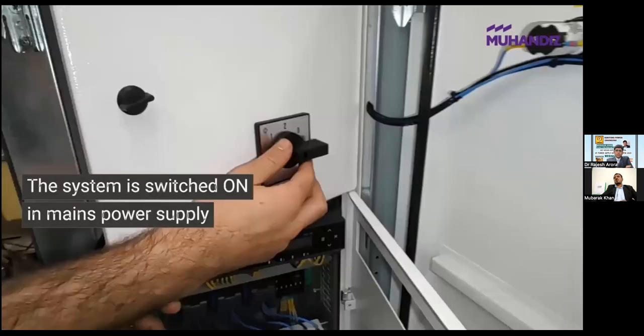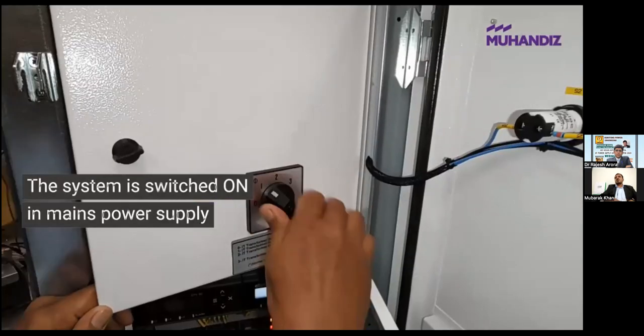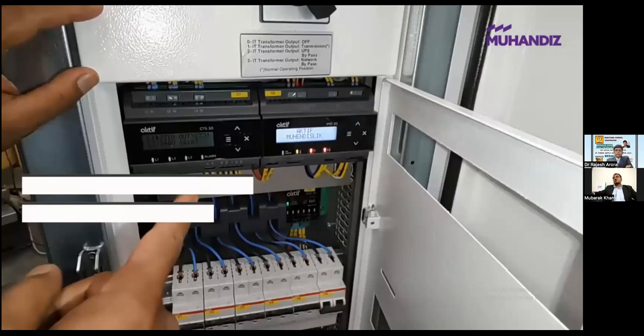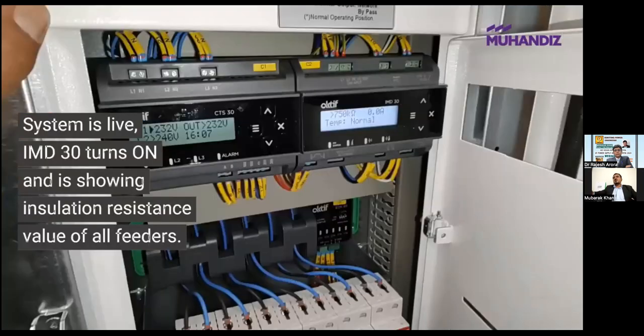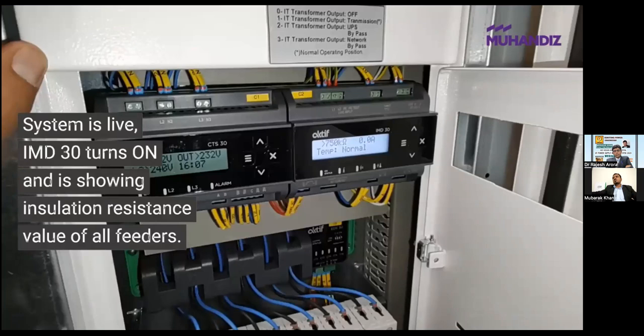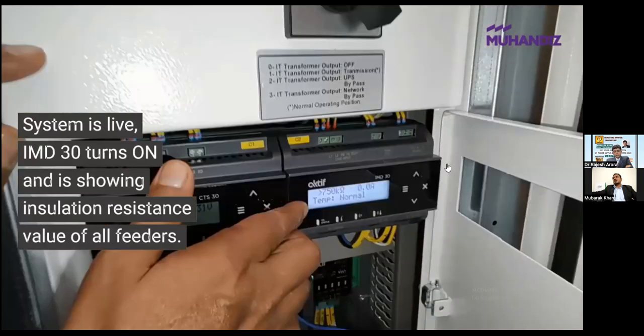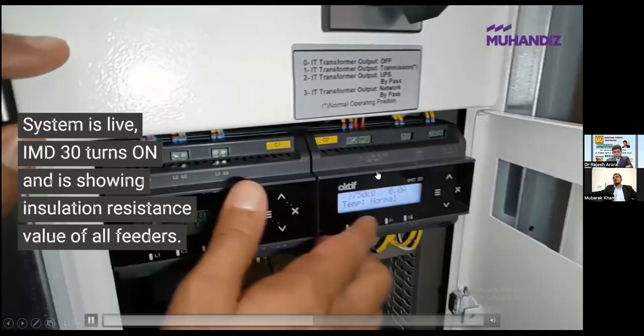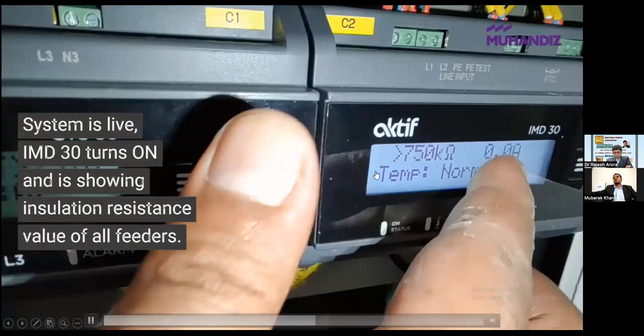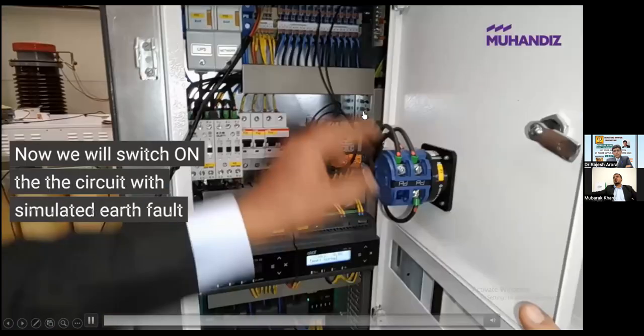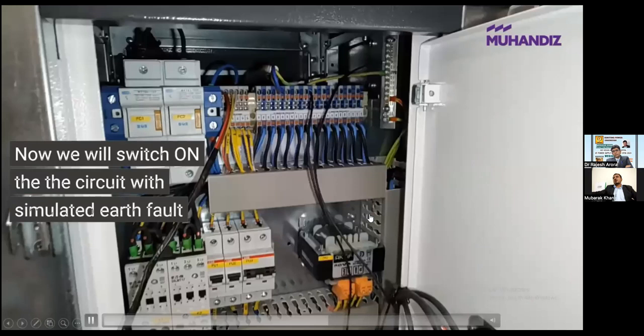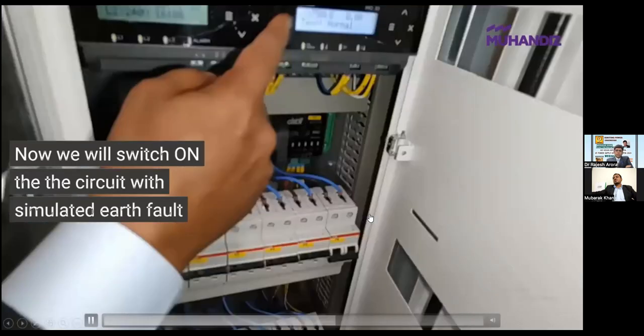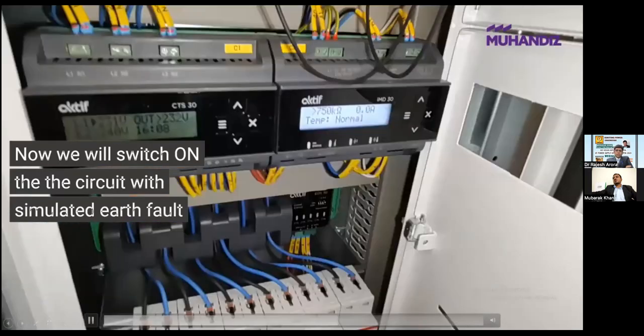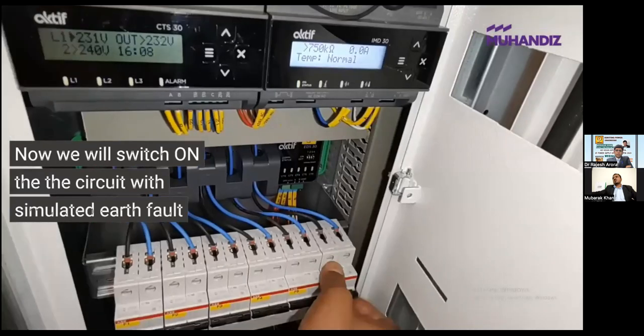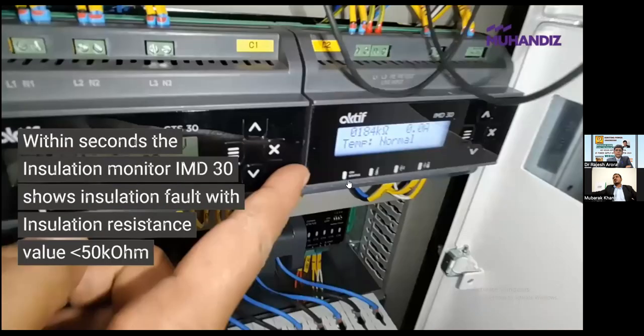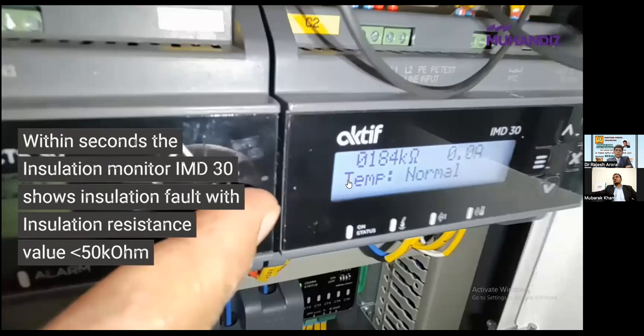Now I'm switching on the power of the panel. The changeover switch and the insulation monitoring device have turned on. It is displaying a 750 kilo ohm resistance, which is very healthy, and no test current here. System is normal. Okay. Now I will switch on the faulty circuit. Then the alarm should come. Okay. So I have switched on the faulty circuit. Now you can see less than 50 kilo ohm and the alarm has come.